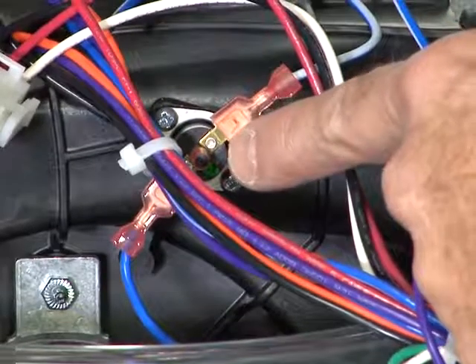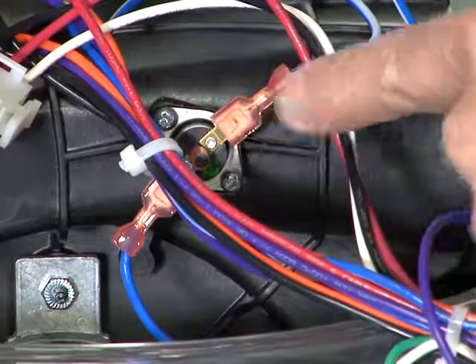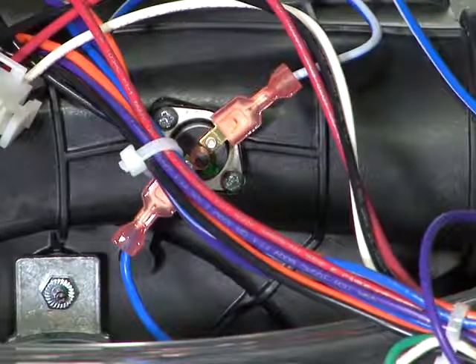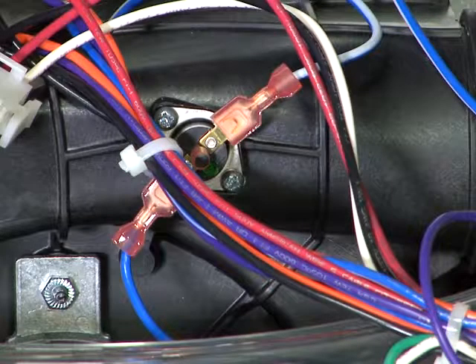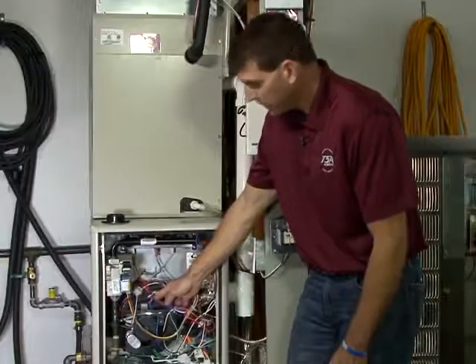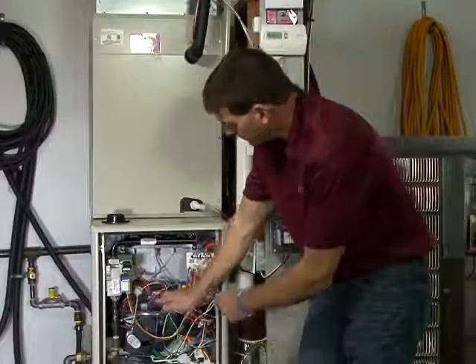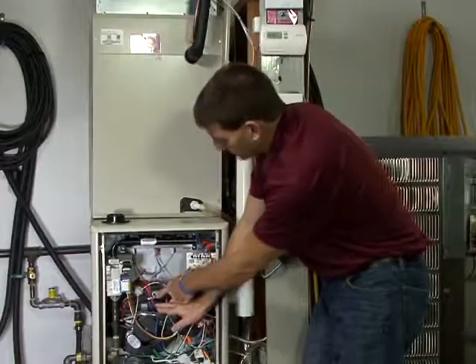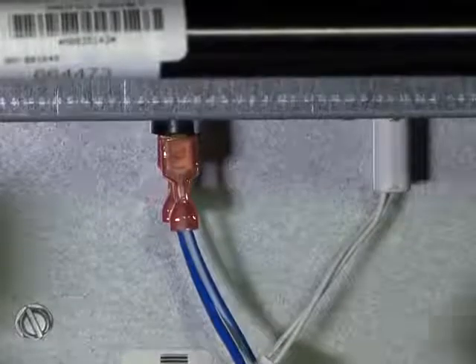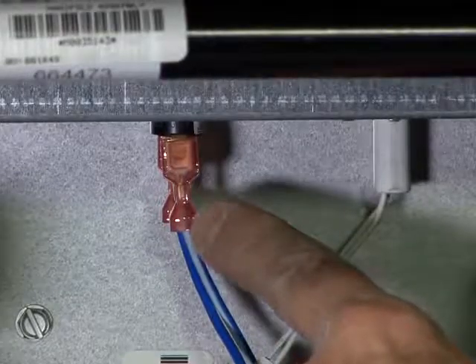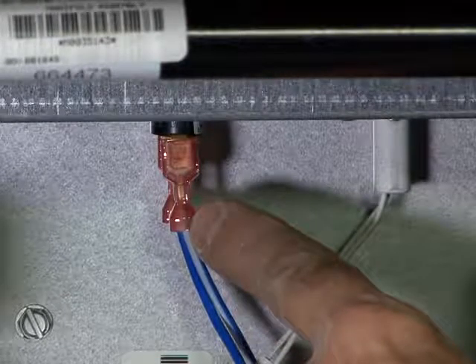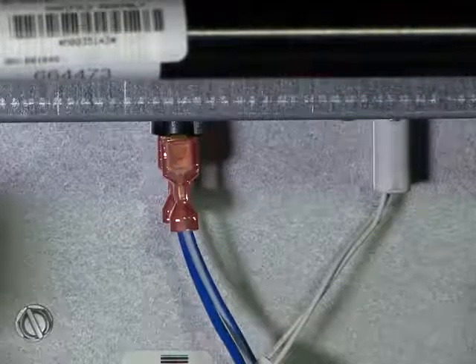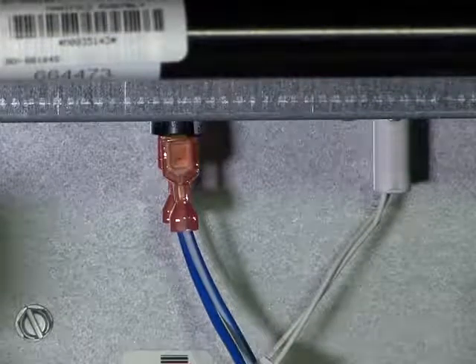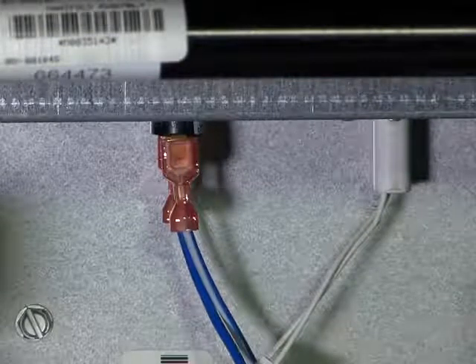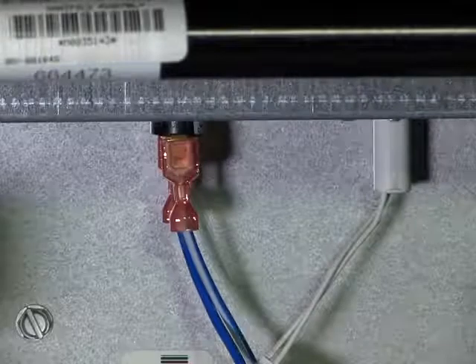Our next switch is a vent limit switch. This monitors the temperature within the vent piping system. This is a manual reset type switch. If this switch is open, you'll have to press the red button to reset the switch. In our main burner compartment area, we have a flame rollout switch that's mounted below the burner assembly. This is also a manual reset type switch. So if this switch were to open, you'll have to press the red button to reset the switch.